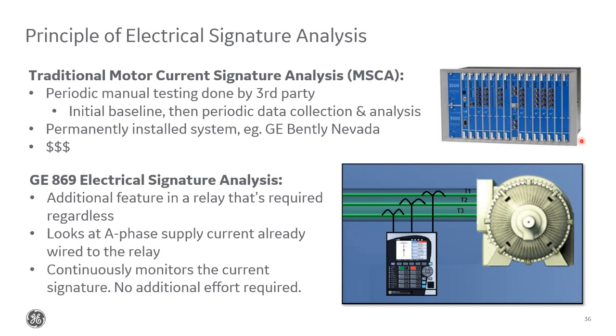Again, the concept itself is not new. Some people have a third-party company come in and do testing where they initially take a baseline reading to see what the normal healthy values are. Then they come back periodically to take a sample and do a comparative analysis to see if anything is changing. Or there are systems like this that can be permanently installed and do this monitoring continuously. Either of these options can be fairly expensive, but the measurements and analysis are usually extremely detailed.